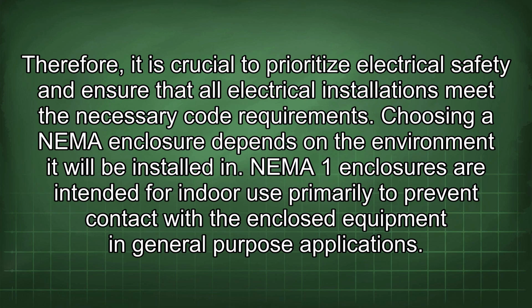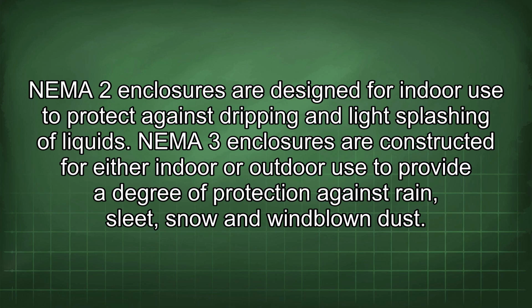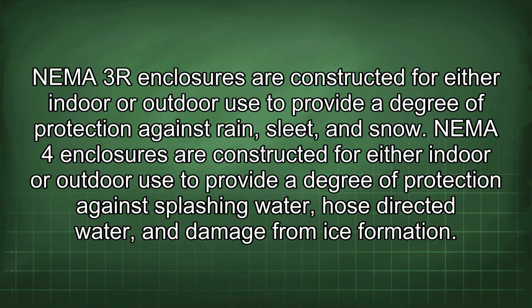NEMA 1 enclosures are intended for indoor use primarily to prevent contact with the enclosed equipment in general-purpose applications. NEMA 2 enclosures are designed for indoor use to protect against dripping and light splashing of liquids. NEMA 3 enclosures are constructed for either indoor or outdoor use to provide a degree of protection against rain, sleet, snow, and wind-blown dust. NEMA 3R enclosures are constructed for either indoor or outdoor use to provide a degree of protection against rain, sleet, and snow. NEMA 4 enclosures are constructed for either indoor or outdoor use to provide a degree of protection against splashing water, hose-directed water, and damage from ice formation.